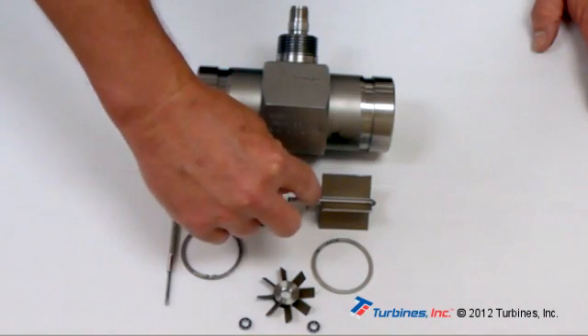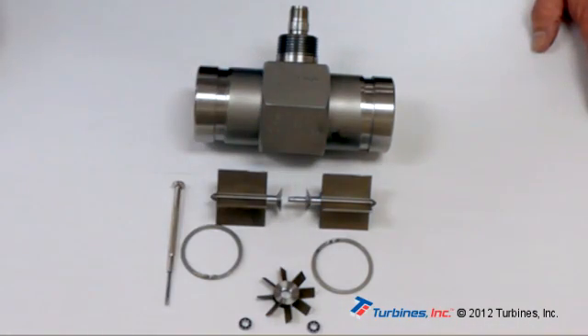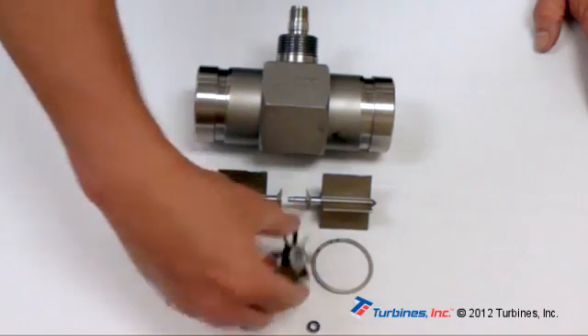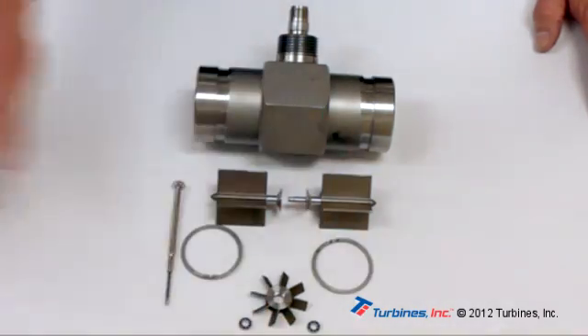On the ends of the cruciforms you will notice the cones. They are to increase the velocity of the product moving through the internal parts of the housing and this gives us a low pressure zone which allows our rotor to balance properly between the cones and minimize friction.